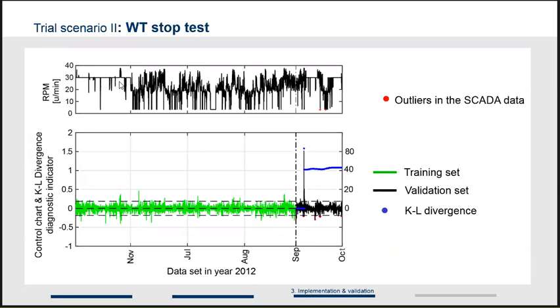Supposing we assumed, okay, let's say now this is confirmed, it's a new information, but I will explain maybe later a little bit more, the idea is that this is most probably a sensor malfunction. So basically it produces flat values of RPM measurements for even changing wind velocity speeds, and the operation is not stopped or anything, but the sensor doesn't measure values in a proper manner.